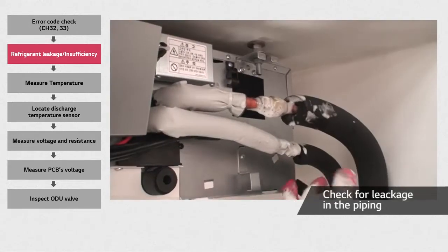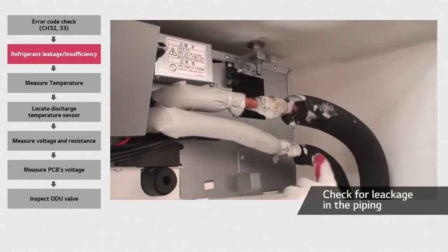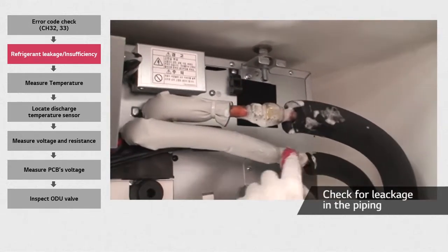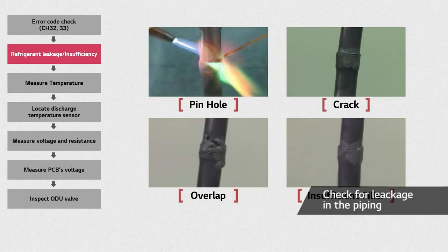To make sure there are no refrigerant leaks, check for bubbles. Also, check that the piping is not deformed.